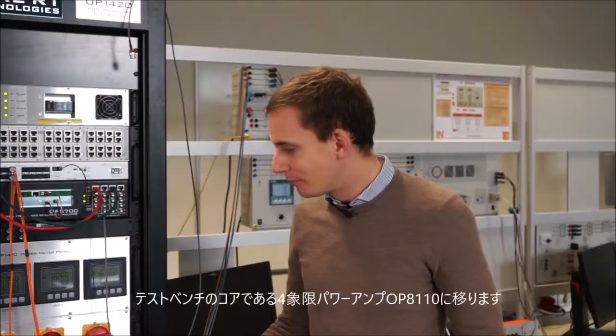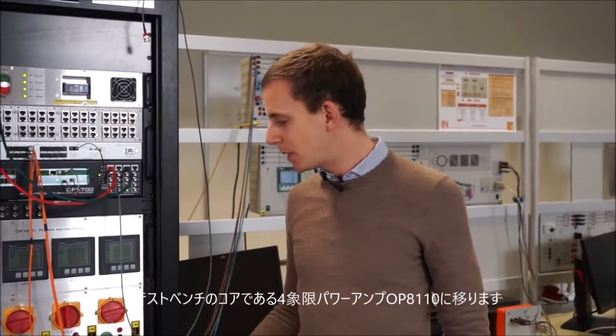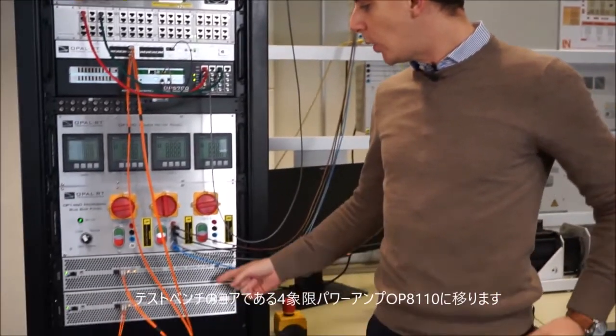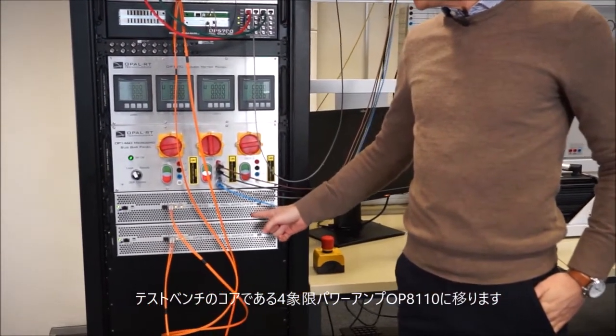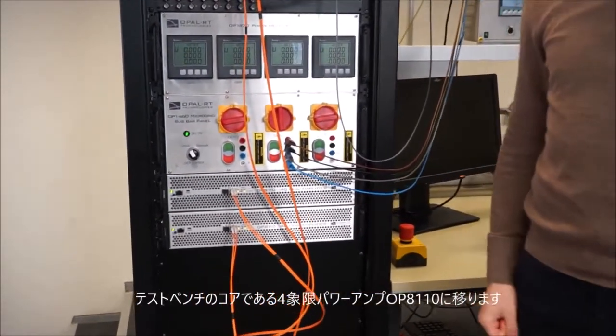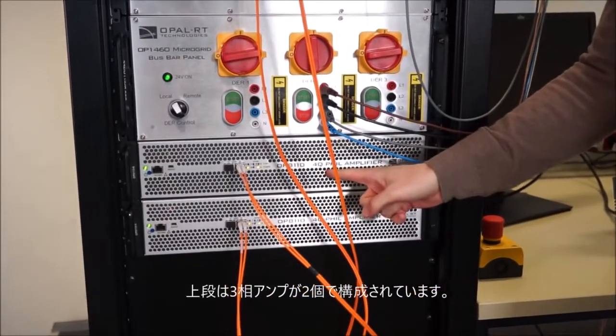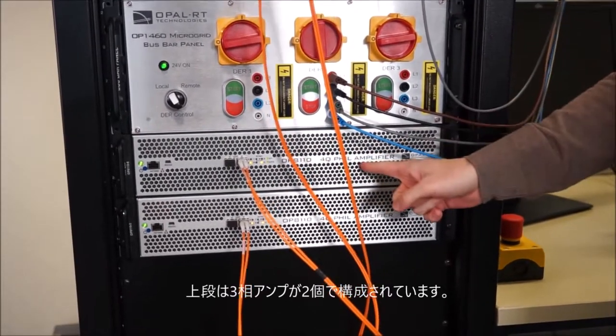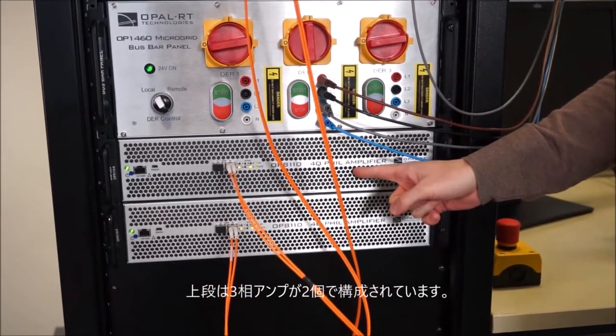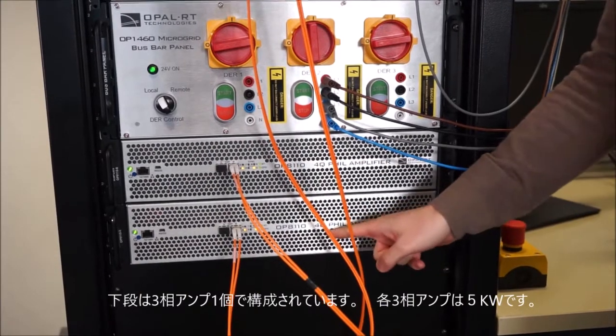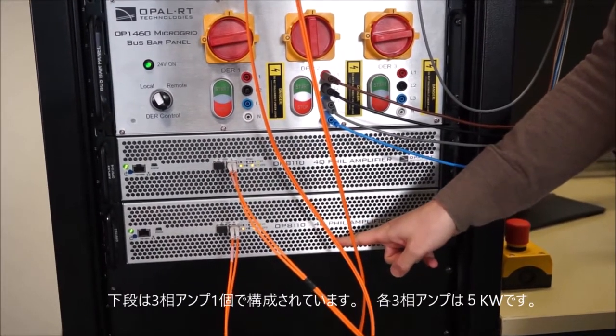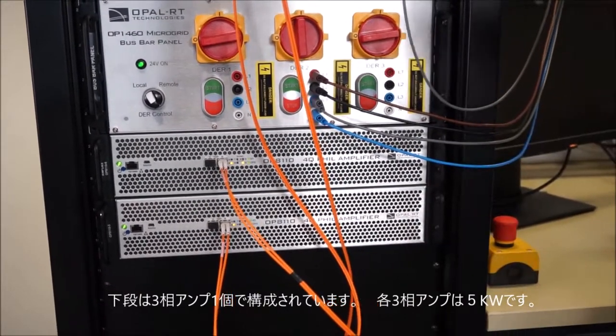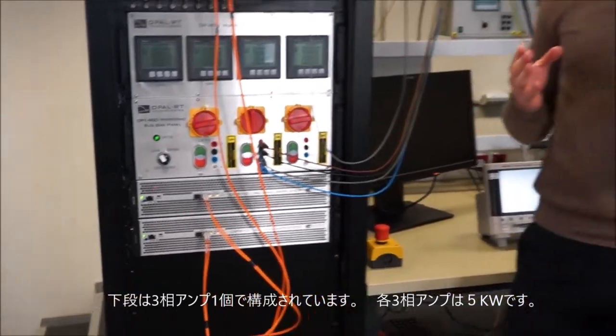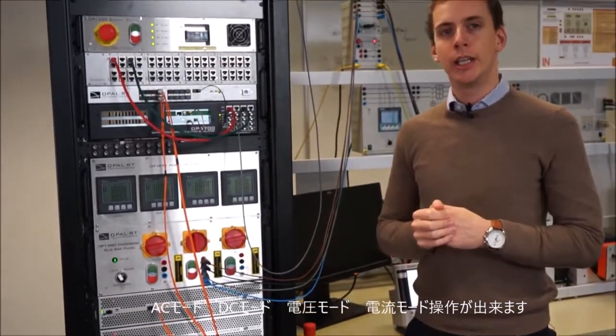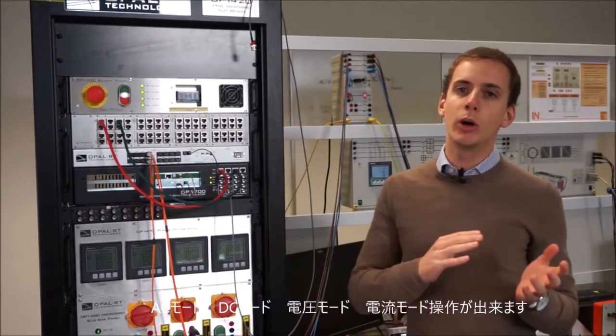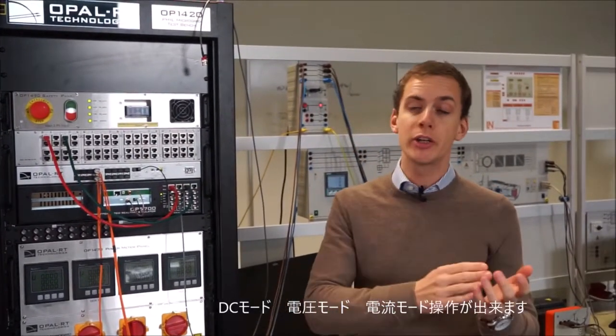Let's switch to the heart of this test bench with the OP8110 4-quadrant power hardware-in-the-loop amplifier. This one is composed by 2 groups of 3-phase amplifiers, while this one is composed by 1 group of 3-phase. So each group has 5 kilowatts, and it can be operated in AC mode, DC mode, voltage mode, and current mode as well.